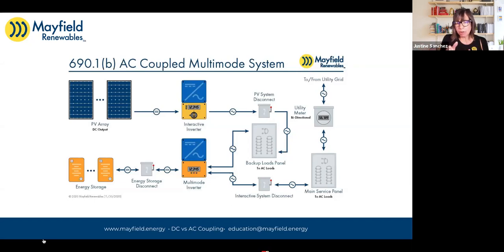You want to make sure the multi-mode inverter's charge control mechanism, for when the grid is down, ensures the energy storage doesn't get overcharged when you're not using much power - because you've got a big array and potentially a lot of energy coming through the inverter, and you need a way to shut those inverters down if the batteries are full. That's what the frequency shift does. However, I wouldn't always assume that's the case - I'd do some digging, call inverter manufacturers, and make sure they're okay with the charge control scheme between these inverters, and that the frequency shift method will work for them.